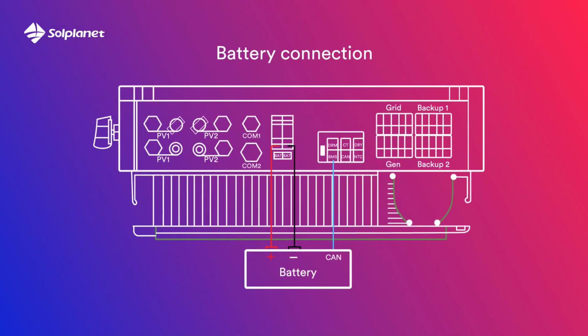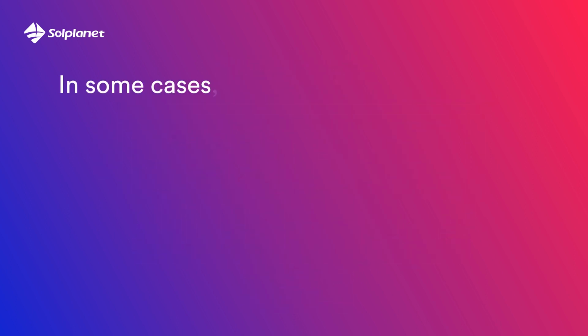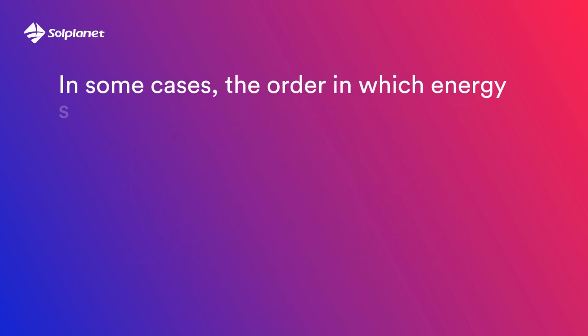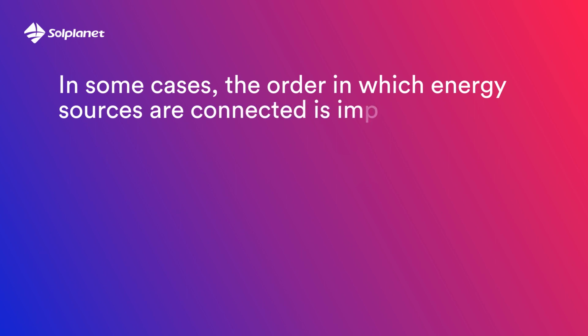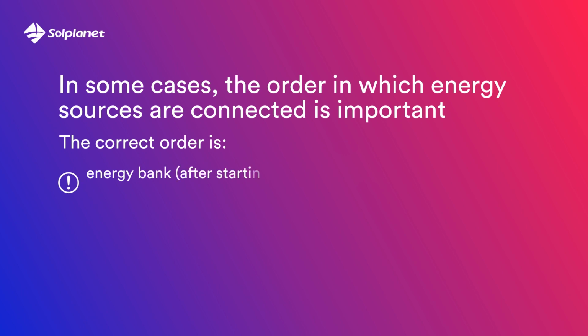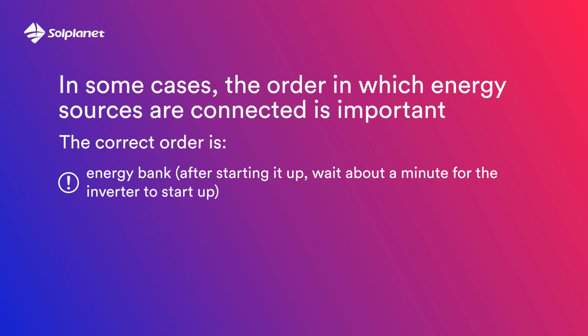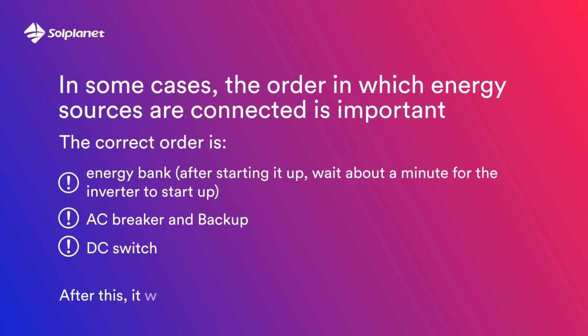In this picture, you see how to connect the batteries correctly. Remember to connect the BMS inverter socket with the CAN battery socket. It is important. In some cases, the order in which energy sources are connected is important. The correct order is energy bank. After starting it up, wait about a minute for the inverter to start up, AC and backup breaker and DC switch. After this, it will be okay.